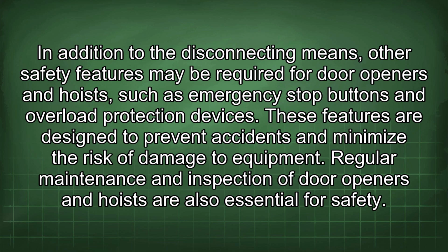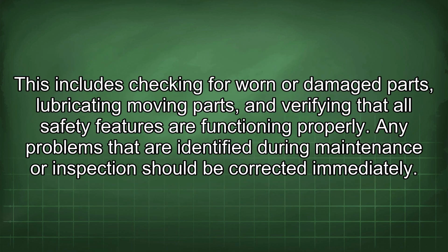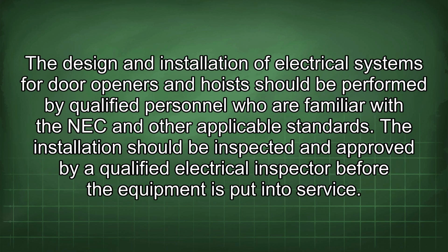Regular maintenance and inspection of door openers and hoists are also essential for safety. This includes checking for worn or damaged parts, lubricating moving parts, and verifying that all safety features are functioning properly. Any problems that are identified during maintenance or inspection should be corrected immediately. The design and installation of electrical systems for door openers and hoists should be performed by qualified personnel who are familiar with the NEC and other applicable standards. The installation should be inspected and approved by a qualified electrical inspector before the equipment is put into service.